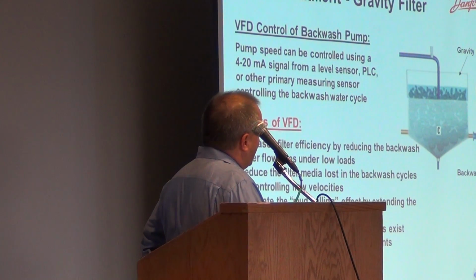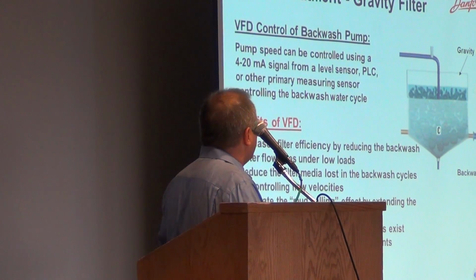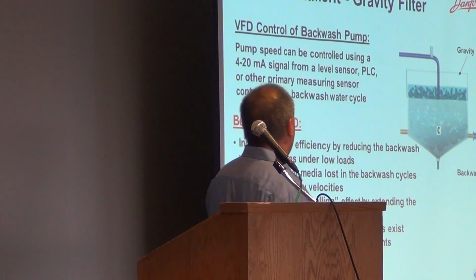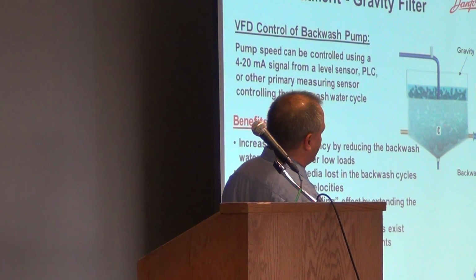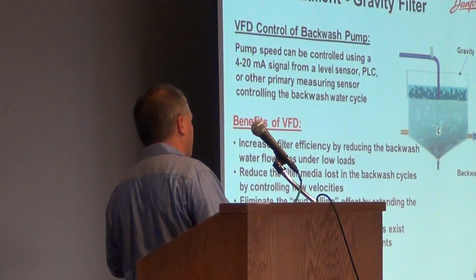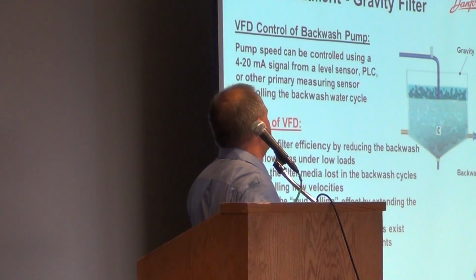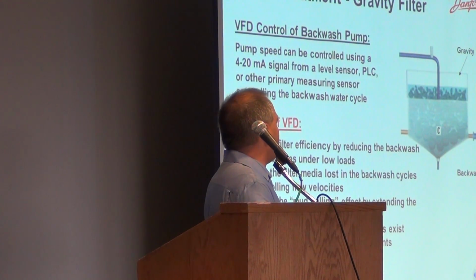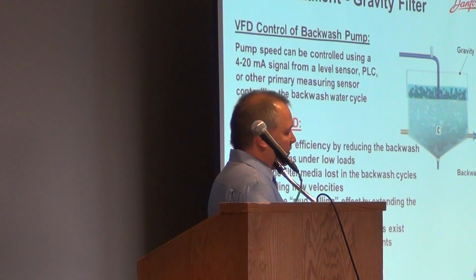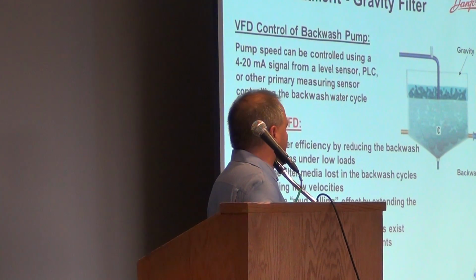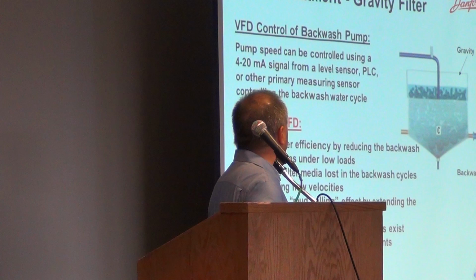I was talking about the backwash on the filters. With a VFD on there, you're not getting the large splash of water through there. We can maintain the flow through the filter. We can get a better flow through the filter so you're not mixing your levels and get a better backwash to use. With treatment plants that have sand filters, we've worked with sand filters. There's no disadvantage to putting a drive on a filter.